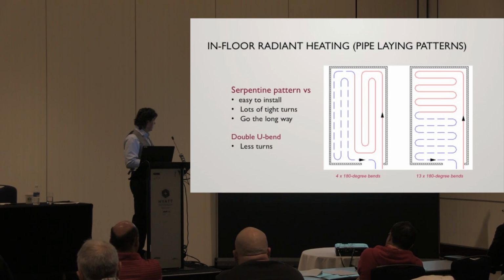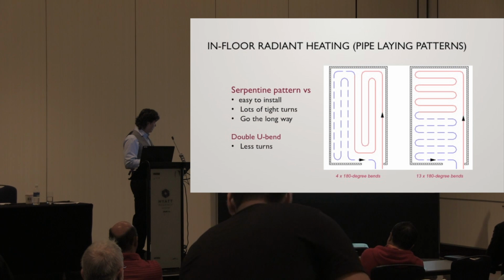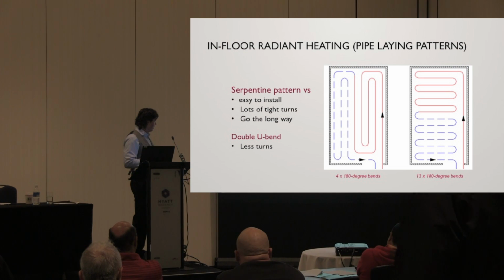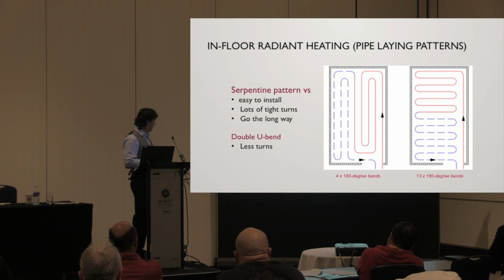The difference is here, if you do it the simple way, which is fine, but you notice you got a lot of fairly tight turns here, like 13 180-degree bends. If you use the reverse, I call it reverse return, also known as W bend, and when you think about it, you got 1, 2, 3, 4 180-degree turns. The rest are 90. It doesn't really take a lot of planning to do this, to say, oh, let's measure 3 feet over and go over, back, leave room, and away we go. It's not that hard to do, honestly. And you wind up with less potential for kinks.